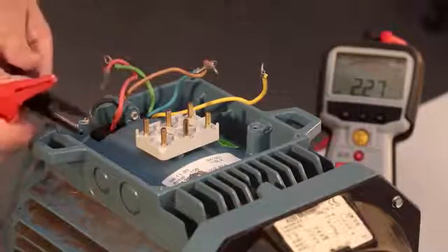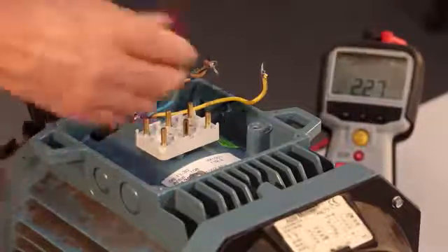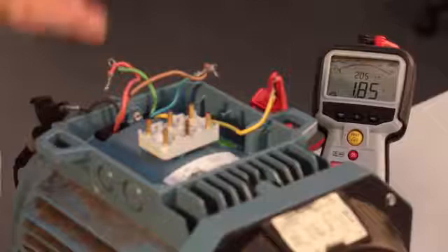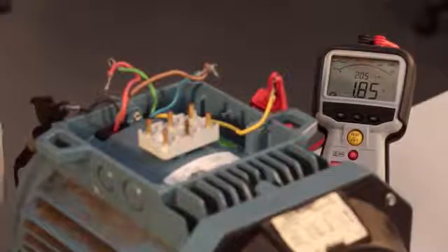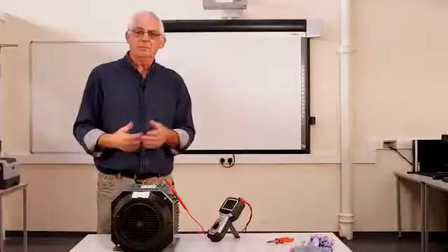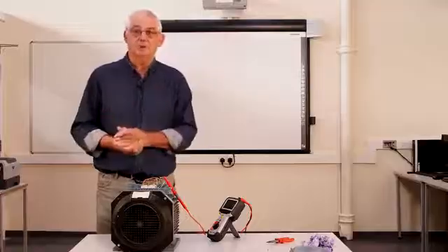So same process, make sure it's nice and tight, touch it together, 1.85. So this really is a good motor, the resistance of the windings are exactly the same. And I can now proceed to connect it up and know full well that it's going to work perfectly.